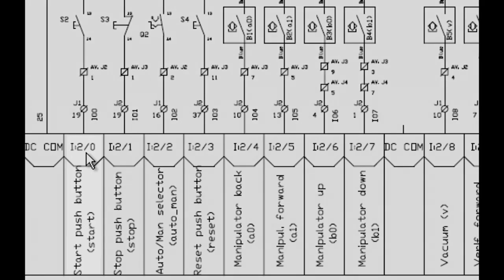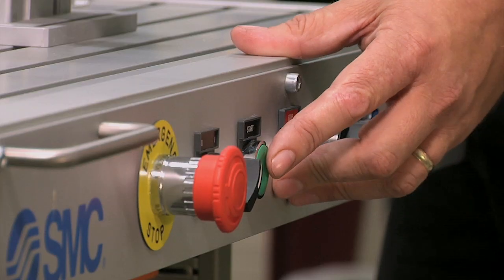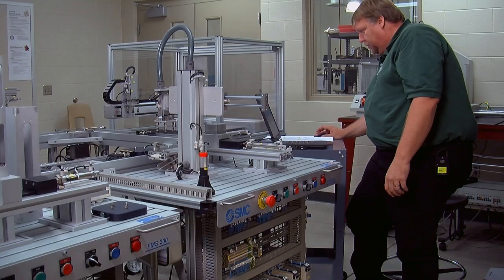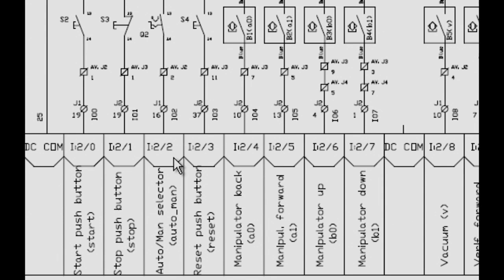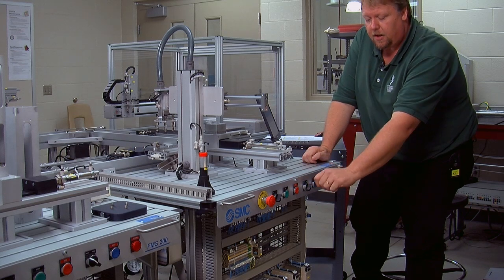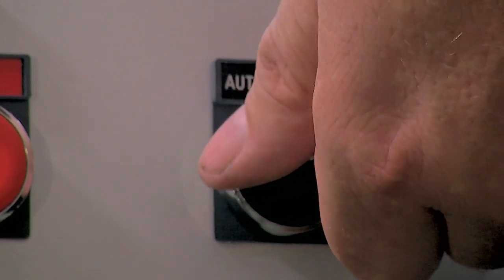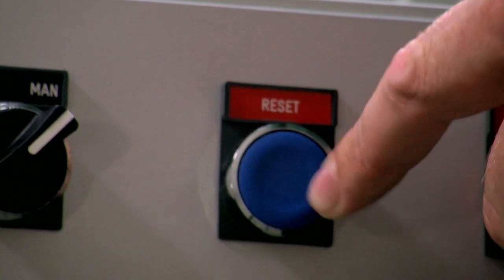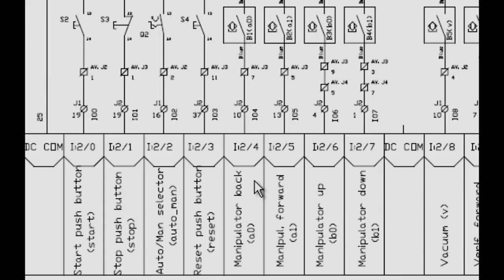I want to go over this a little bit closer. I:2/0 is the start push button — you can see it right here, this would be the push button. Our next one is our stop push button, located right here. Next we have auto/manual, which is I:2/2. This is a two-position switch but it only has one address, so in one position you get a signal, in the other you won't. You program accordingly. Our next button is I:2/3, and this button enables us to reset the station should our actuators get out of control or out of sequence.